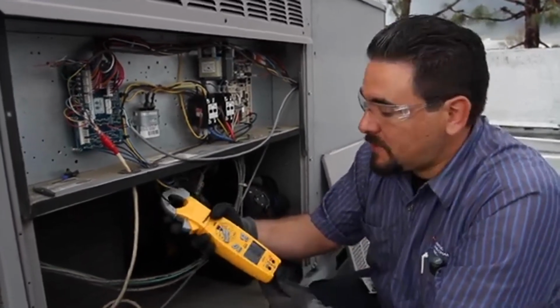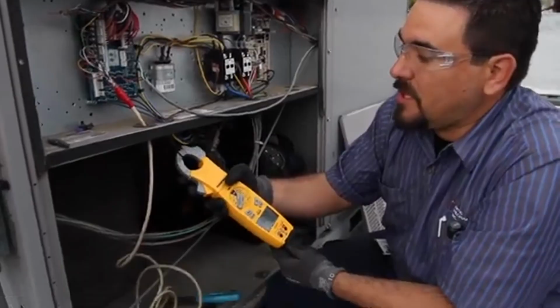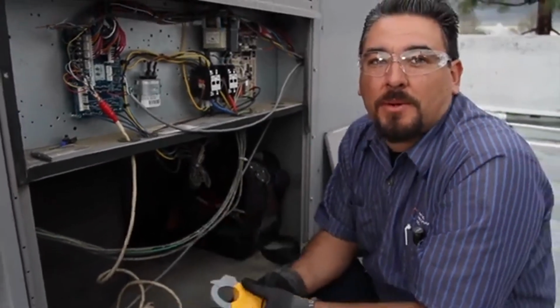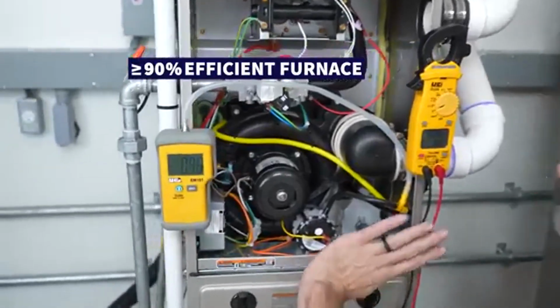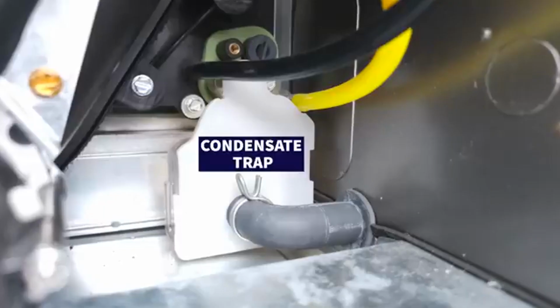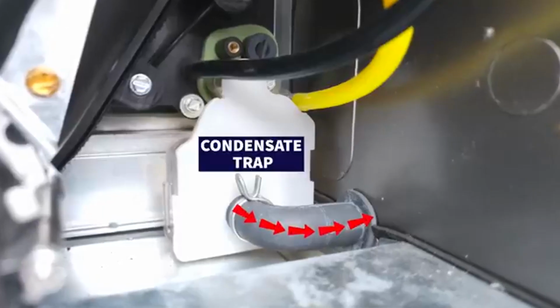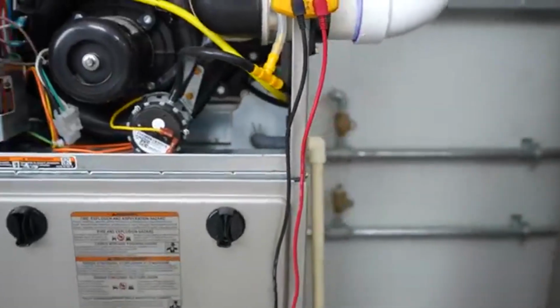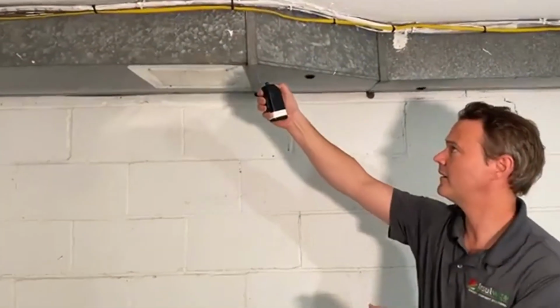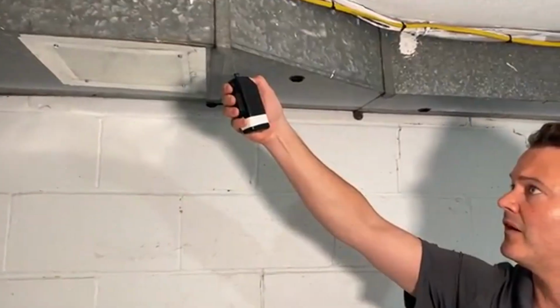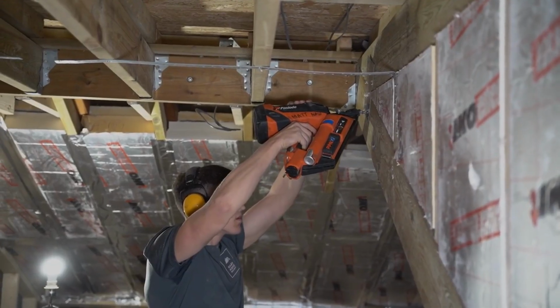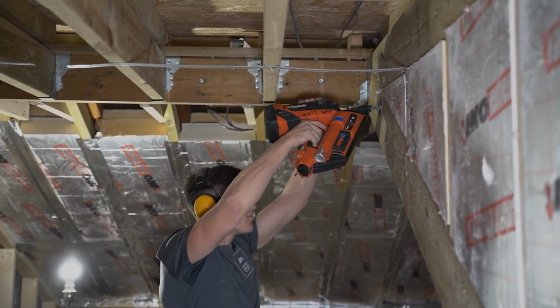Now, sometimes the equipment really is the problem. If your system is 15 to 20 years old and you've got documentation of regular maintenance and the ducts have been checked and they're reasonably tight, then yeah, replacing aging equipment makes sense. But do the diagnostic work first. The duct repair might cost you $1,500 and solve 80% of your problem without touching the equipment at all.